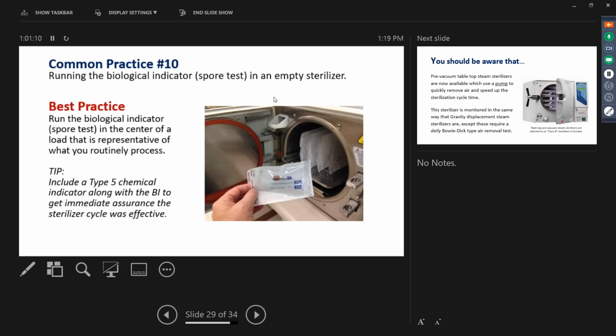Number 10 is they do run a BI, but they run an empty sterilizer during it at the facility, and that doesn't do them a lot of good. They're supposed to test what they do. So if an empty sterilizer can pass, what about an overloaded sterilizer? That's what I want to see.